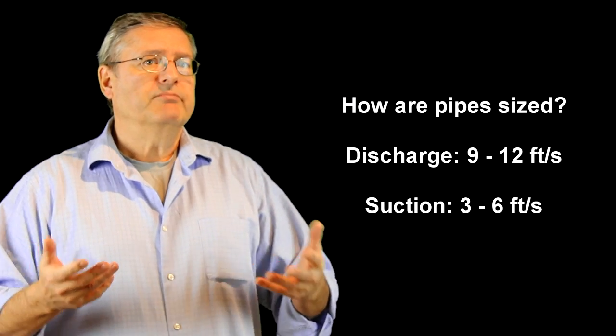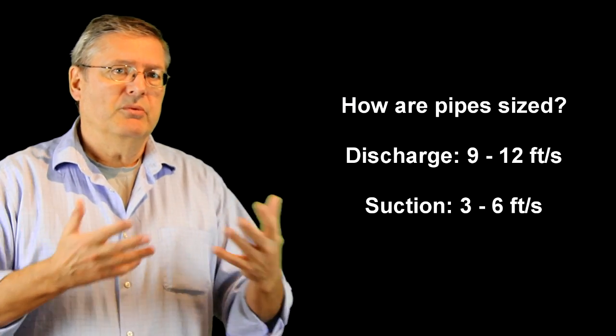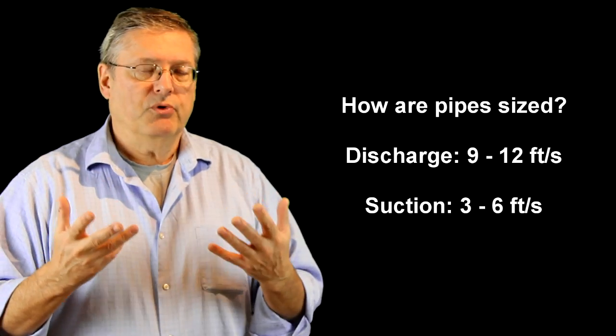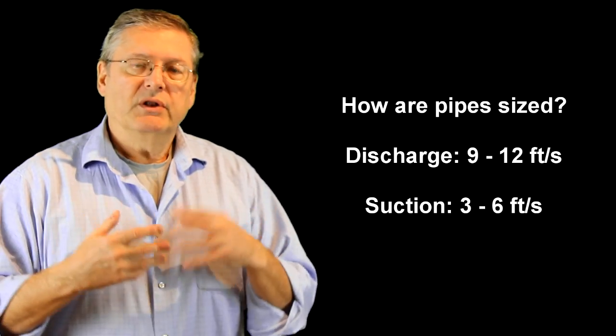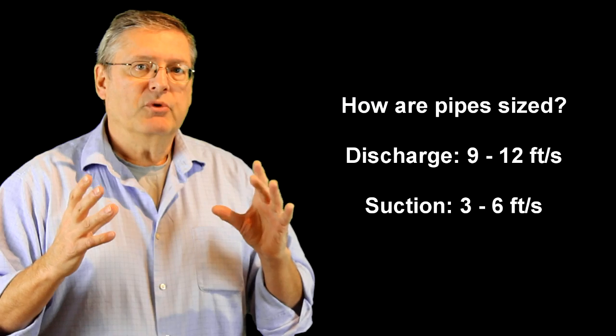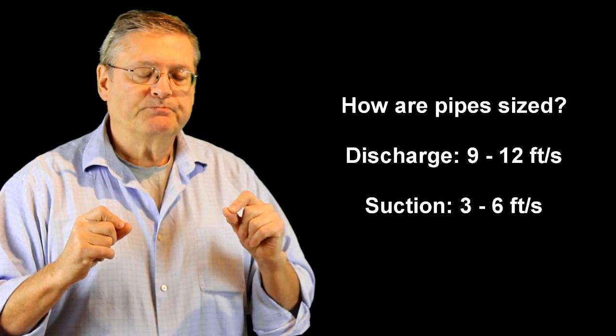On the suction usually we'd like to be a little bit slower, maybe between three and six feet per second, but again this is entirely variable. Very often it will wind up being approximately one pipe diameter above the size of the suction, but again depends on the specific situation.